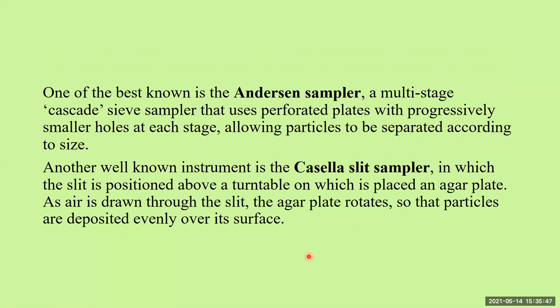One of the best-known impaction samplers is the Andersen air sampler. It is a multi-stage cascade sieve sampler that uses perforated plates with progressively smaller holes at each stage, allowing particles to be separated according to their size. There are six stages with six different plates, placed one above the other. Through the perforations at each stage, bioaerosols enter and are deposited on the surface of the agar plate, with different-sized particles collected at each level.